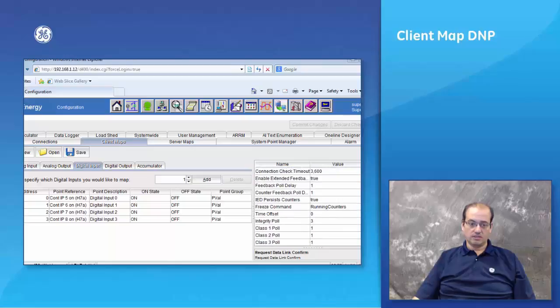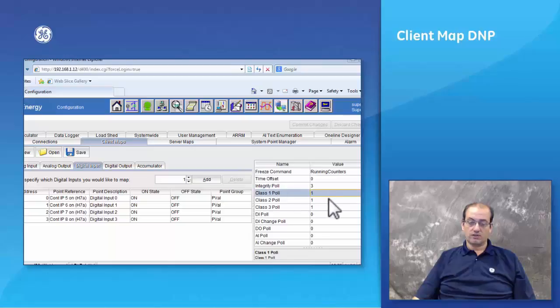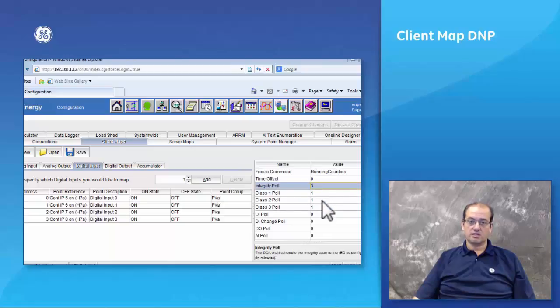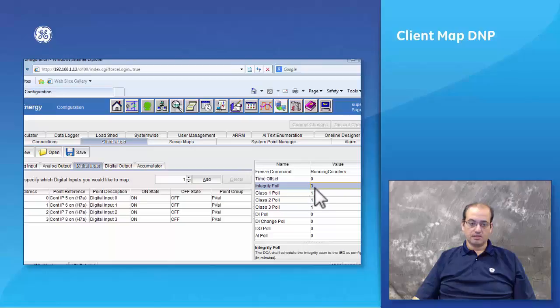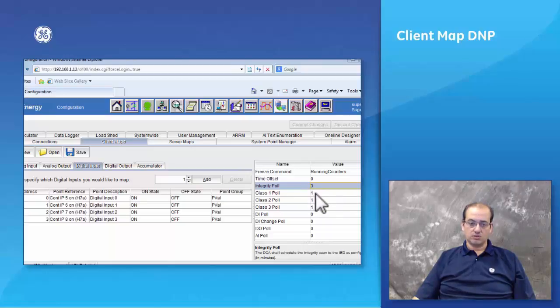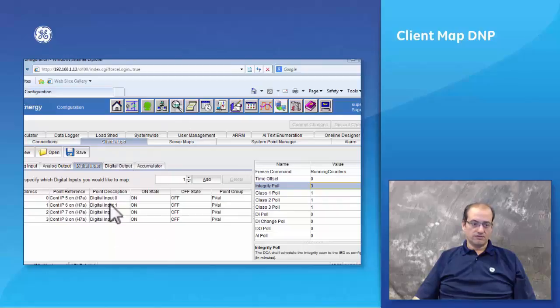The properties of the client map is defined in here. We're doing a class one poll every one second, we're doing an integrity poll every three minutes. If you are wondering about the timing for these parameters, you can get it from our user's manual from our technical website.